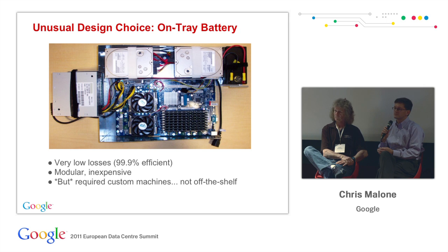The traditional model of building a massive UPS room and slowly fitting out your server room means you spend the CapEx up front and your efficiency isn't great for a long time. This allowed us to trickle charge the UPS, so the effective efficiency is ridiculous—approaching 100%. When it's needed for transition to generator or so on, you take a small hit.